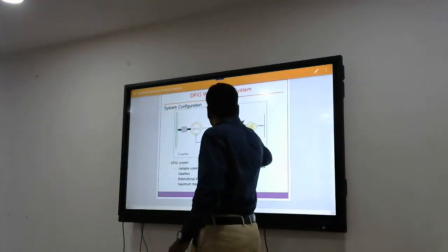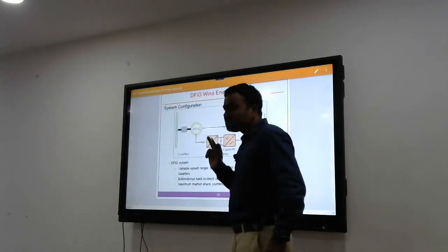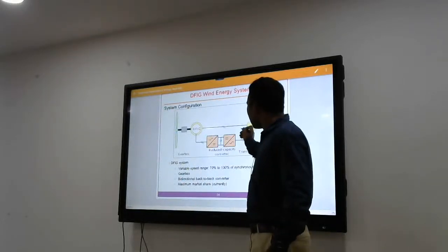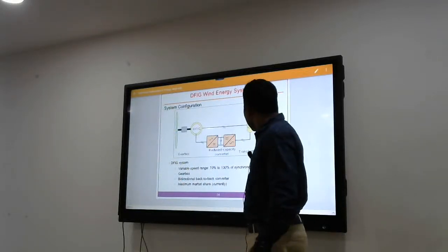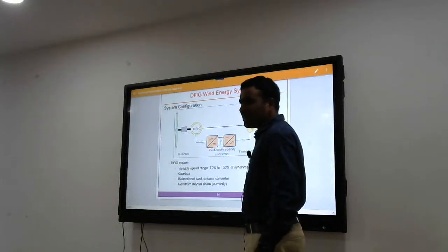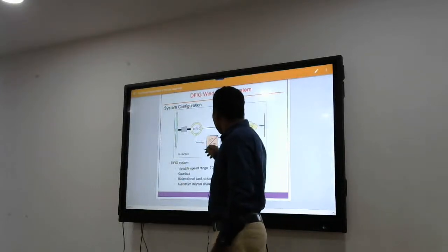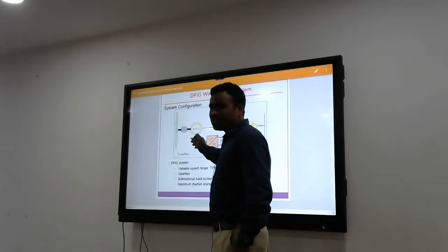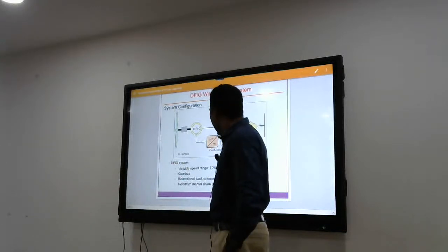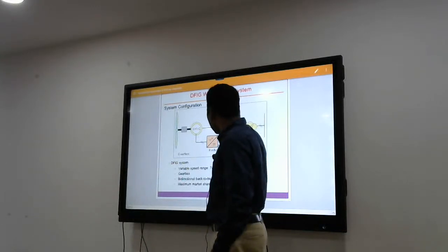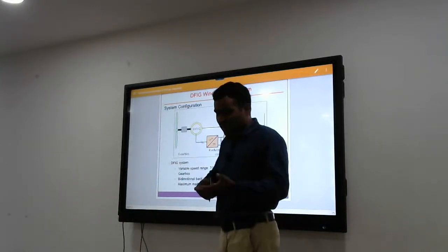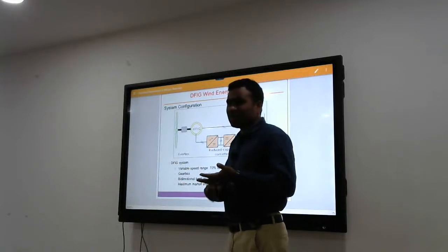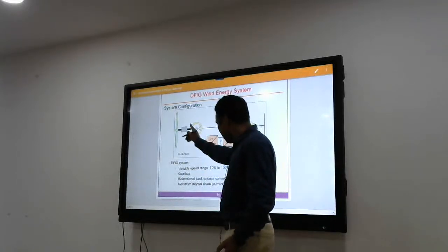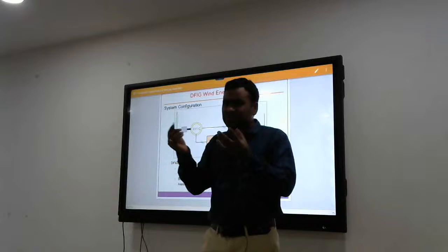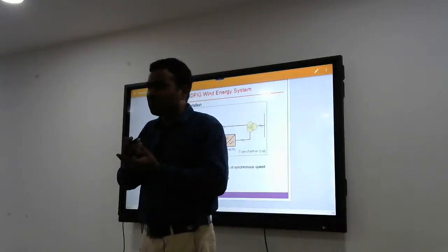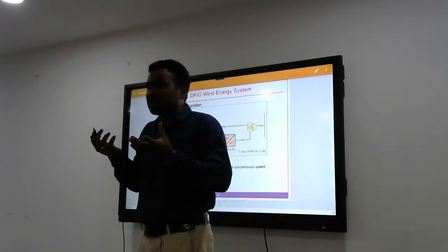Okay. In this case, one advantage I told here: for getting power of 1.3 per unit, your power electronic converter that is required is 0.6 per unit. It means the converter requirement is very less. That is the one advantage. The other advantage is the rotor voltage is also slip times stator voltage.